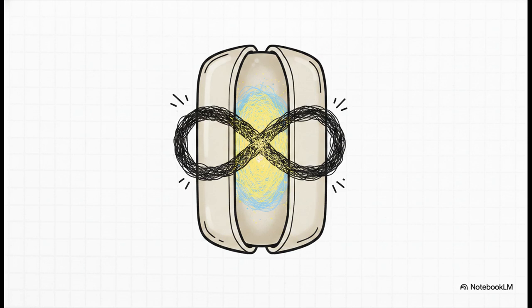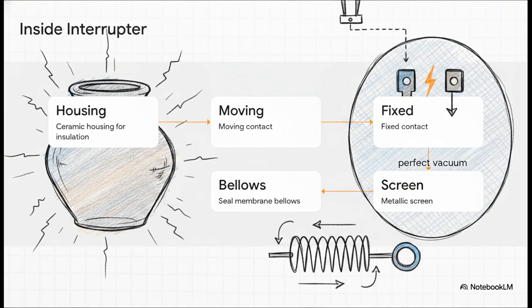Okay, so we've got the external nameplate specs and the fuse coordination locked down. Let's shift gears and actually look inside the unit. We're going to mentally crack open the sealed ceramic vacuum bottle, which is formally known as the vacuum interrupter. This little sealed unit right here is the beating heart of the contactor. It's the exact reason the V-Contact series can pull off a staggering, totally maintenance-free lifespan of 100,000 operations. Breaking down that internal anatomy, we start with a highly durable ceramic housing, which gives it both mechanical strength and intense electrical insulation.